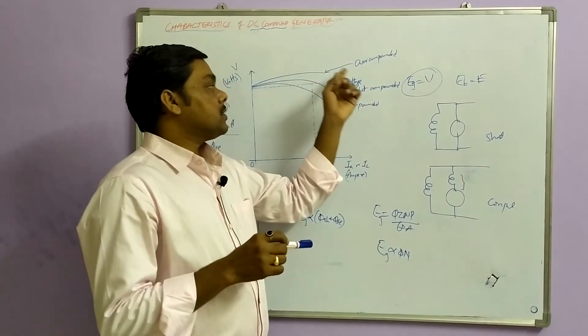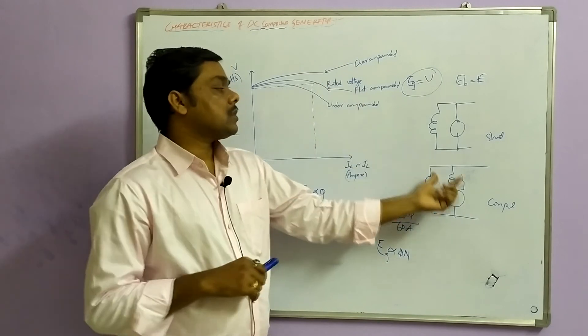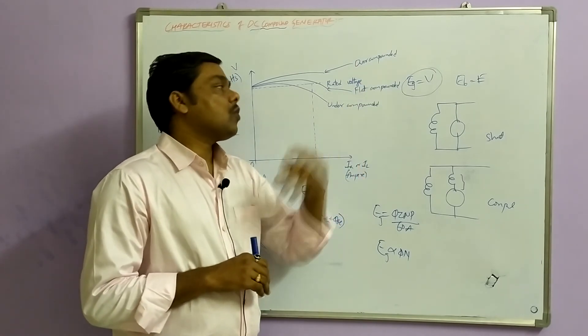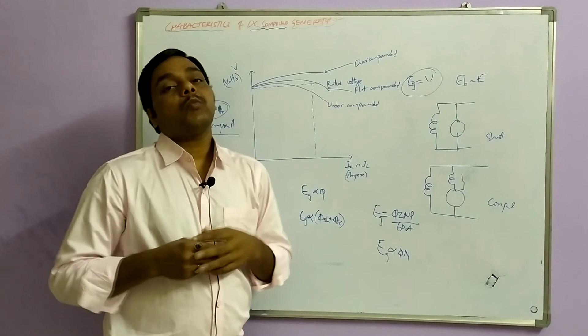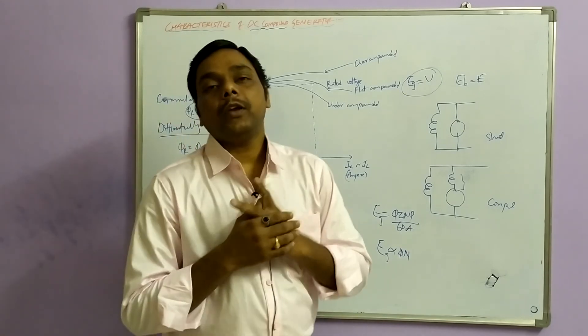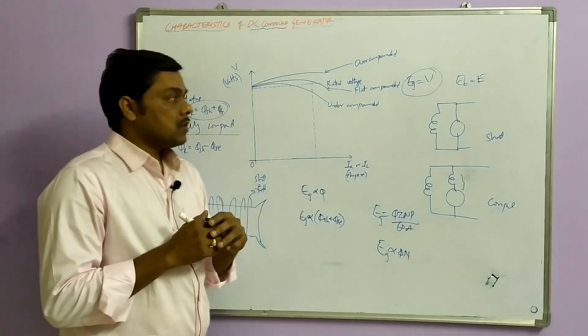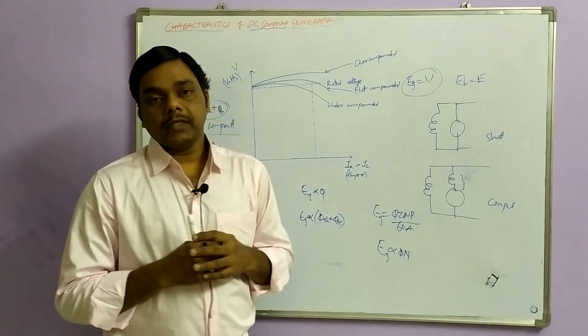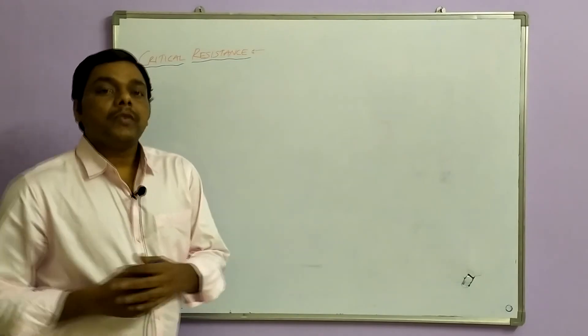Depending on our applications, we can use extra series turns to keep the voltage constant. This gives us flat compound, under compound, and over compound generators. Generally, over compound generators are used in industrial purposes so that voltage drop is less when loaded and they can operate at rated voltage. Cumulative and differential compounds also help maintain constant voltage, and the cross magnetizing and demagnetizing effects are less affected in these generators.